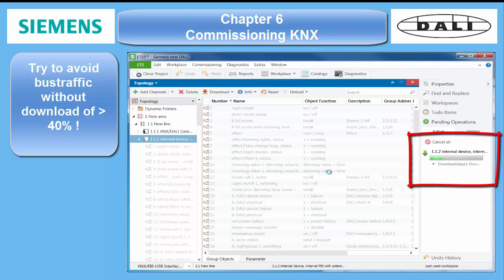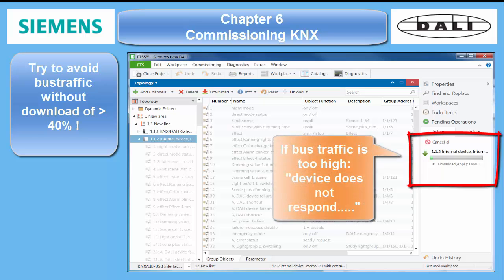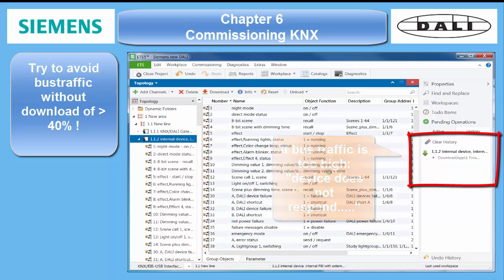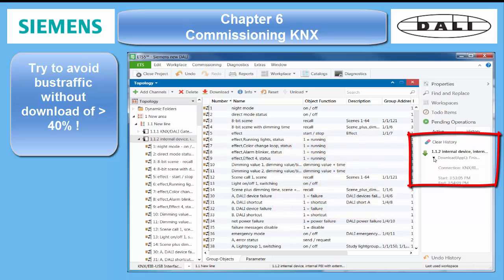At rates of more than approximately 60% already existing busload, interruptions become more and more possible. This may be expressed by messages like 'the device doesn't respond.' Once again, this is normally not a problem of the device, but very likely a problem of the already existing busload.